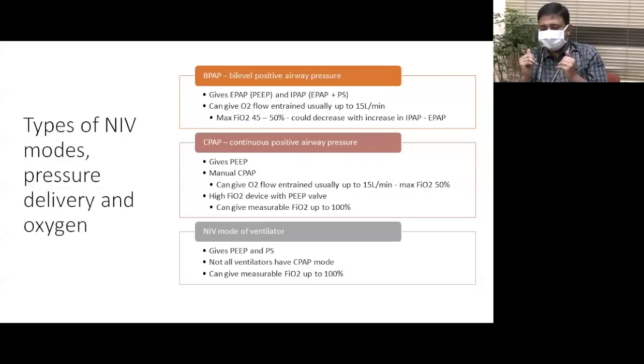Here you have a machine which is delivering pressure, which is driven primarily by air, and oxygen is entrained into the machine. So when oxygen is entrained into it, it mixes with the pressurized air that is going through the tubings and gets delivered to the patient. So the disadvantage is you cannot know the exact FiO2. You can know by putting in a FiO2 meter, you can measure, but that's generally not available, so you do not know. We have worked out some calculations as to what pressures and what flow can give what oxygen. But what is important to note is that you can give only a maximum FiO2 of about 50%. And also, when the pressure support increases, when IPAP minus EPAP, when you're giving more pressure, less oxygen will mingle into the stream.